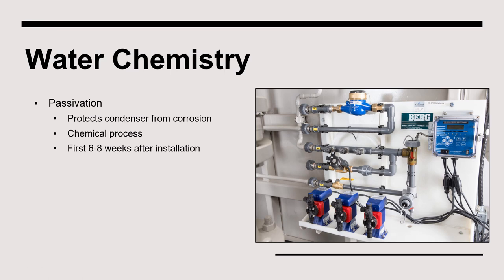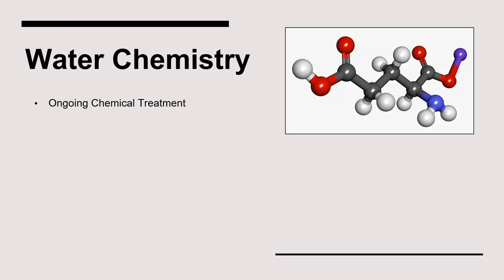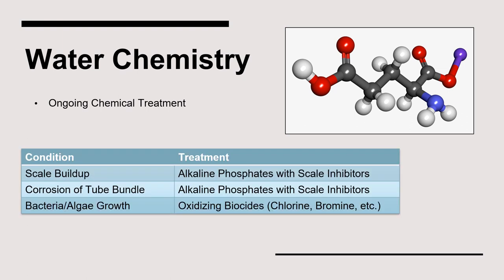Passivation is the process of carefully controlling the pH of the condenser water when it is first placed into operation. During passivation, a chemical process takes place which enhances the original corrosion-resistant galvanized surface of the tube bundles by forming an oxide coating. If passivation is not performed, a condenser's lifetime can be significantly shortened. Once passivation is complete, chemical water treatment continues to be implemented. Several conditions are undesirable, like scale buildup, corrosion, and the development of bacteria or algae. Chemicals like alkaline phosphates, scale inhibitors, and oxidizing biocides are added to the water to manage the condition inside the condenser.